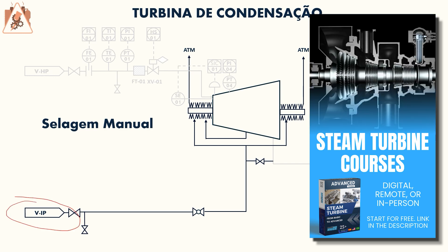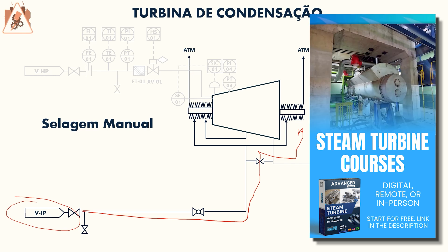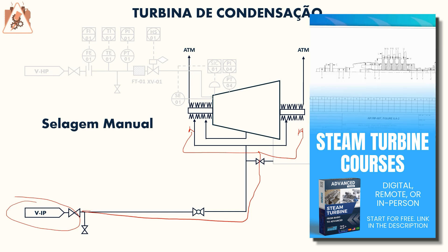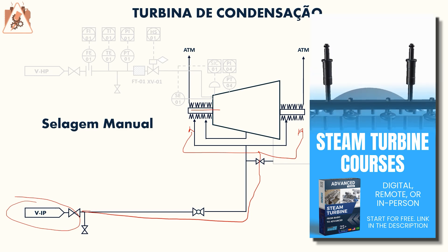Manual sealing is no longer permitted by the API 612 standard, but older machines from the 1960s and 70s may still have this type of seal because at the time it was allowed. Basically, this sealing system consists of an intermediate pressure vapor; we admit steam into the turbine.